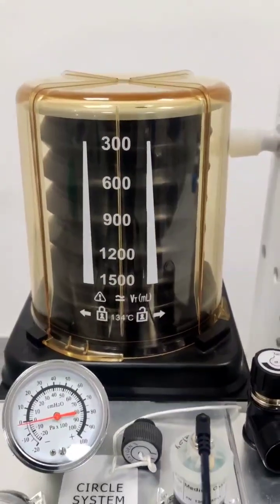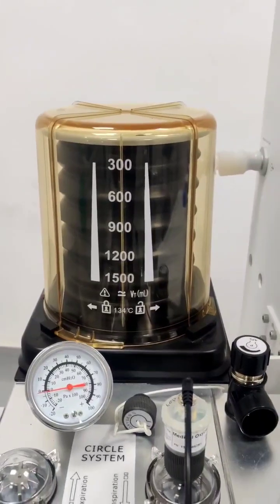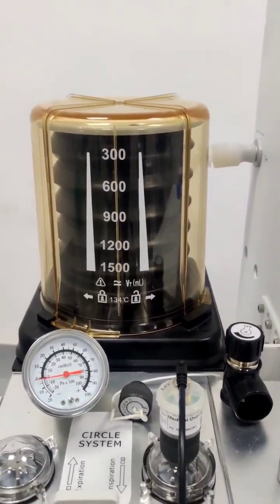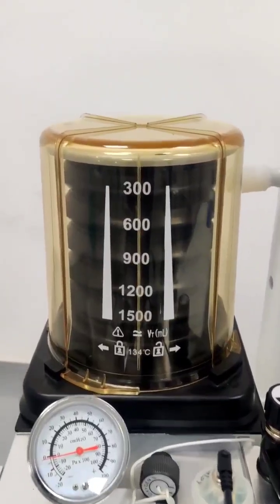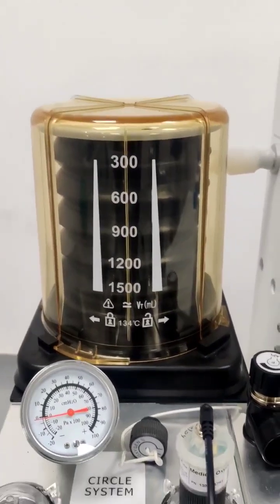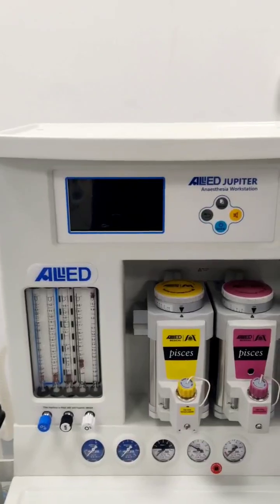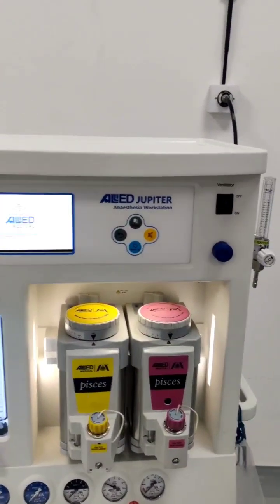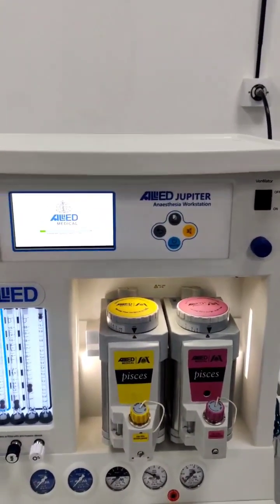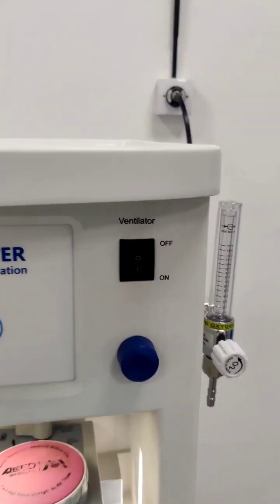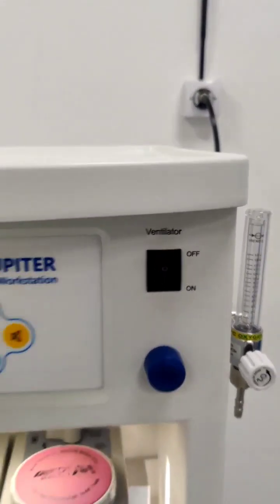Then we are giving the bellows system, which has markings on it. Whatever patient volume is being delivered by the machine will be measured with the help of these markings on the bellows. Now coming on to the ventilator side, this is the turn on, turn off switch of the ventilator. So from here you can turn on the ventilator and turn off the machine also.